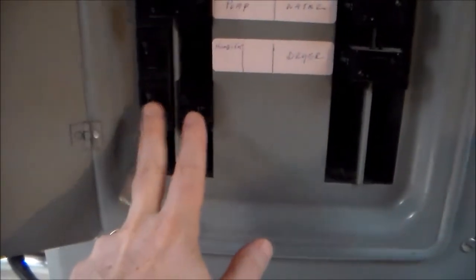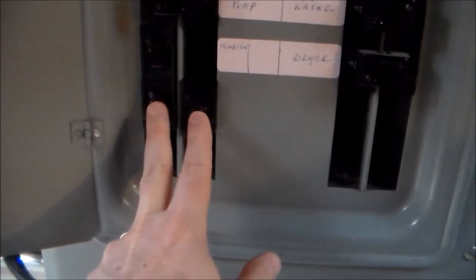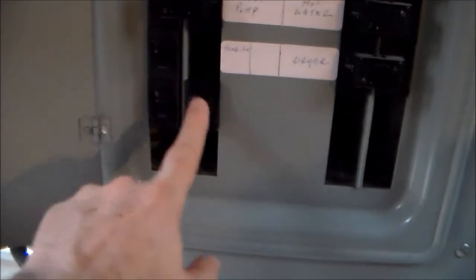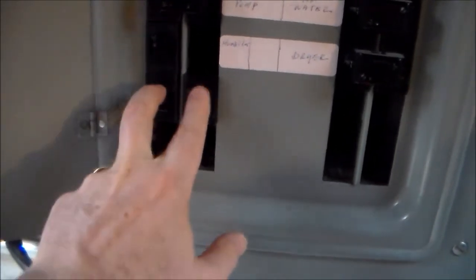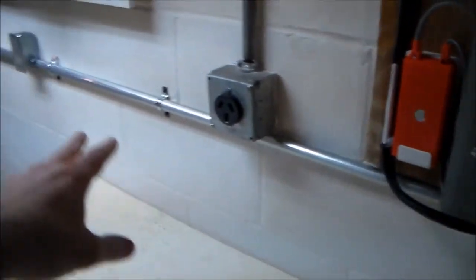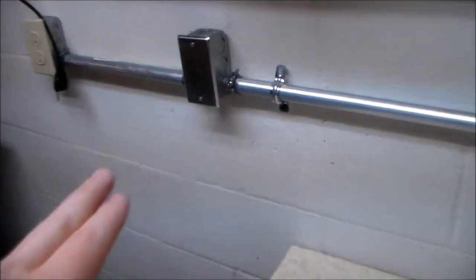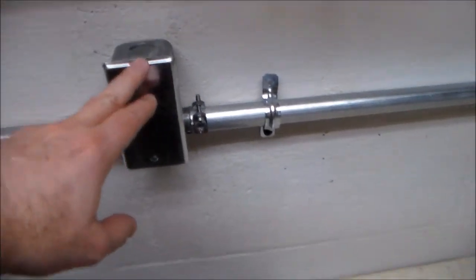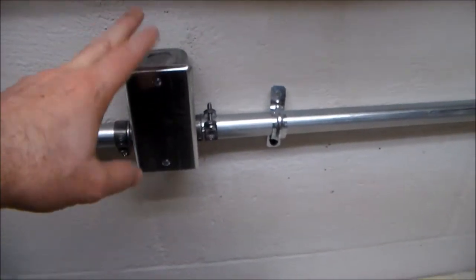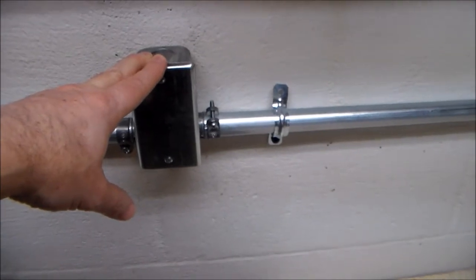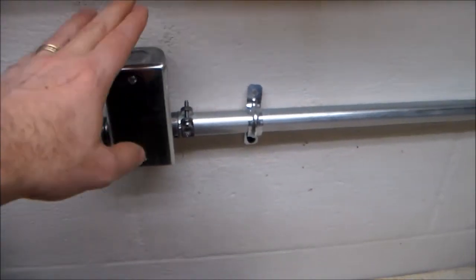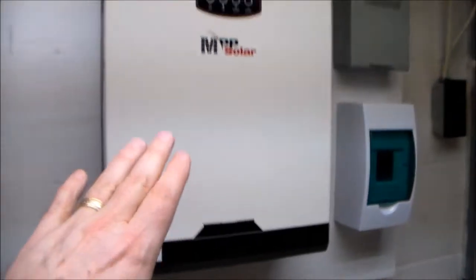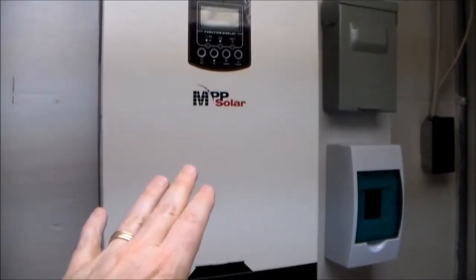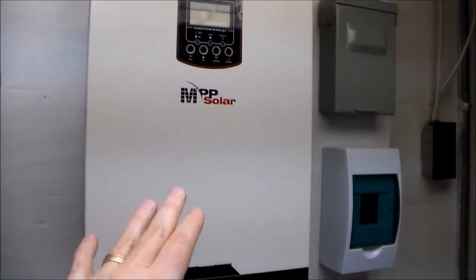And as I mentioned, these are Square D. I don't have these labeled yet, but these are two new Pushmatic breakers. Actually, this is a 15, this is a 20. But those I installed, and that is what runs through this conduit. And so this is going to be a 20 amp circuit, and it's a dedicated 20 amp circuit. That will be the only thing that's on that breaker, and this circuit will feed this device when I'm ready to start wiring it and getting it online.